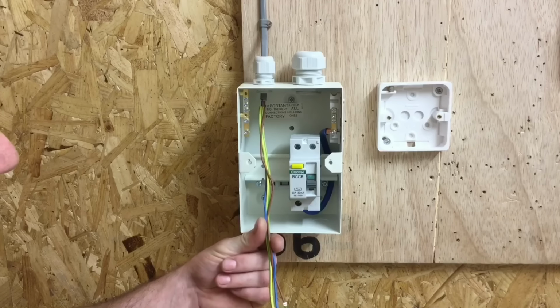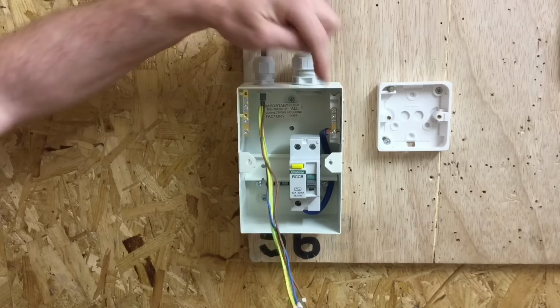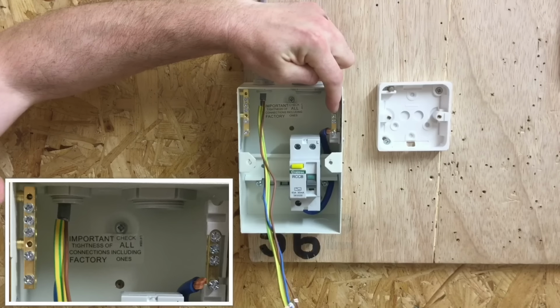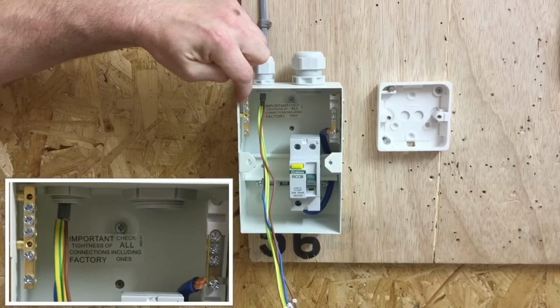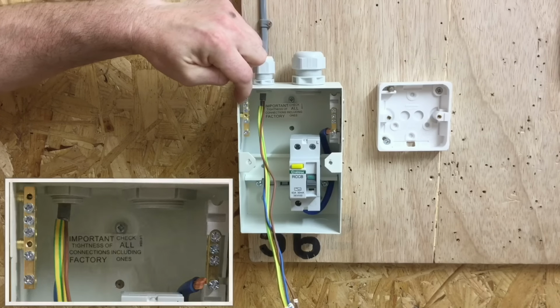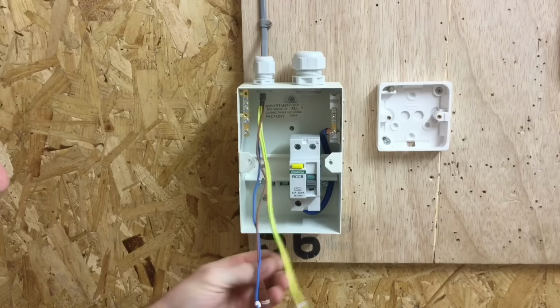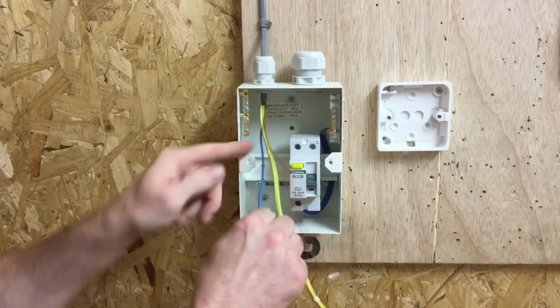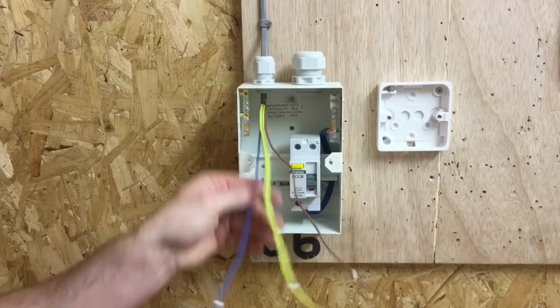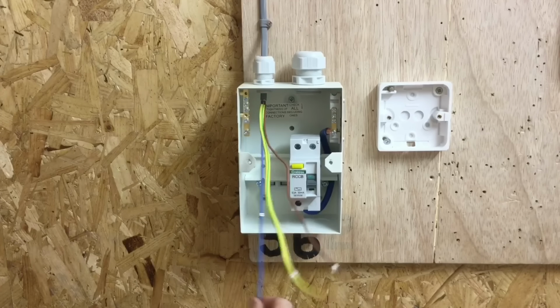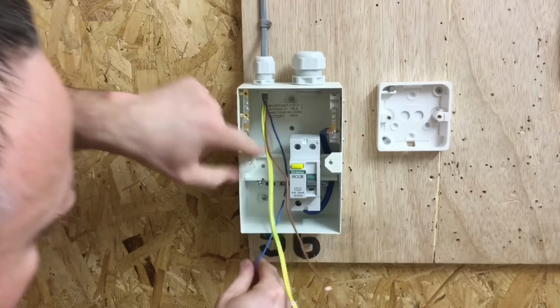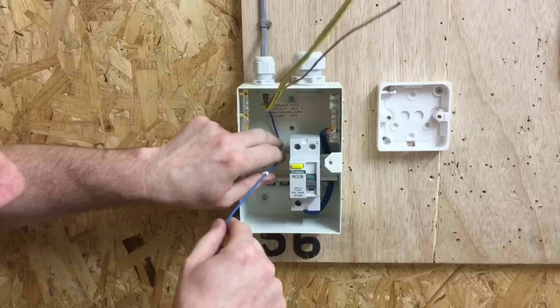So it doesn't matter which order I'm going to terminate my conductors in, but I'm going to use the top termination as number 1 in the neutral bar and the top termination in the earth bar for my circuit protective conductor. Let's start then with the neutral conductor. So as always, I need to get it as straight as I possibly can before I start. So I'll run it through my fingers and we're going to dress it straight down the back. Okay, it's going to be a little bit awkward because I've got to try and get my head out of the way for the presentation.